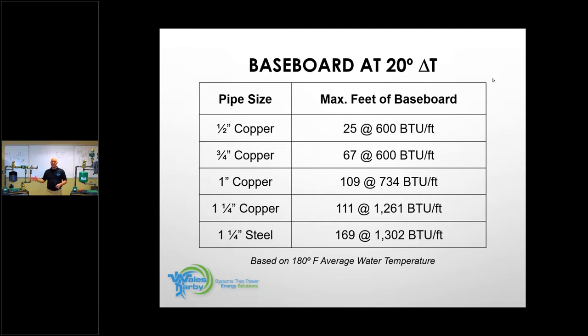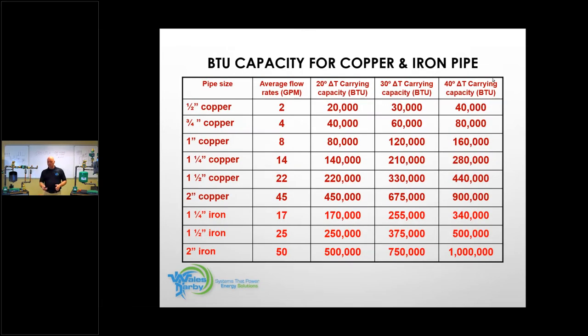And I wouldn't want to go beyond 67 feet of baseboard heat emitter, because I won't have the ability to keep that 20 degree delta T on there, which means I'm going to start delivering less BTU. And you can go right down through this list here and do the math on them and multiply them out, and they will all equal right about here, what we're looking at in this column right here. 20 degree delta T, we're going to carry this BTU based on this flow rate, based on this diameter of pipe. So the most common we use in our industry is 1¼ for manifolding boilers. That's good for about 14 gallons per minute and about 140,000 BTU with a 20 degree delta T.